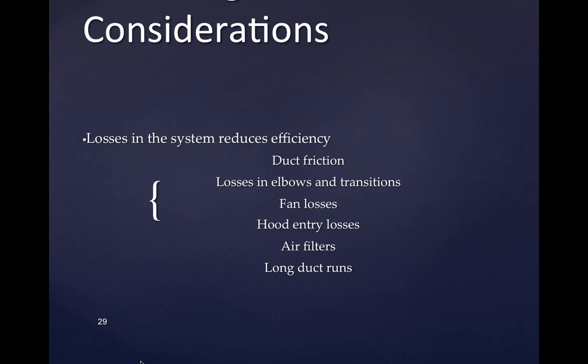So it would sink back down into the. Well, in the horizontal run, he wanted it because he didn't care that much. A lot of times, if you have a vertical run of ductwork and you're dealing with particulate, you'll have a clean out on the bottom. So you're not so concerned about the stuff dropping out, because you usually manage that in one way or another. But on the horizontal run, if he doesn't maintain the transport velocity that he needs, then it'll start to build up in that horizontal run.